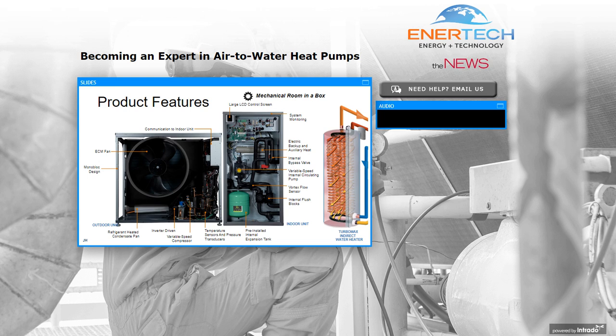One of the big labor savings are these bypass valves. You can see a red device. Those are the zone valves that will switch between heating and domestic hot water, as well as an internal pressure differential bypass valve. So we're able to do all of that inside the box and save quite some time with not only piping, but sourcing components and so forth.